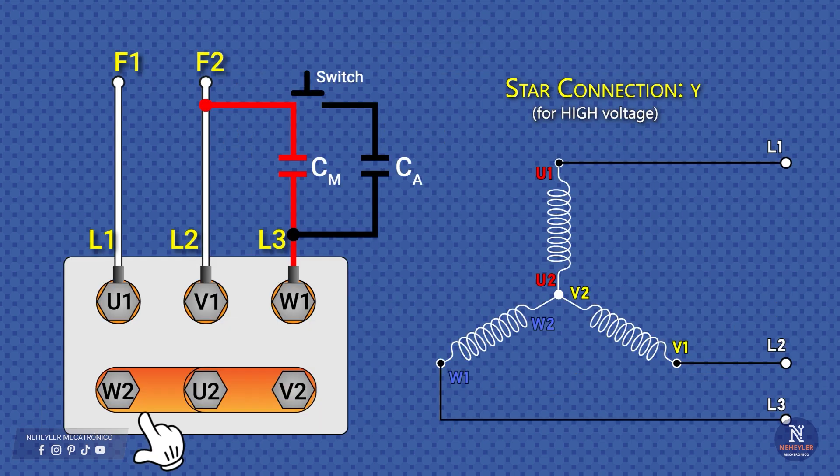In star connection, the terminals U2, V2, and W2 are joined together with metal plates, forming a common point. The supply is connected at U1, V1, and W1. Since in this case we only have two phases, the capacitors must be connected between one of the output points and one of the supply lines, as shown.